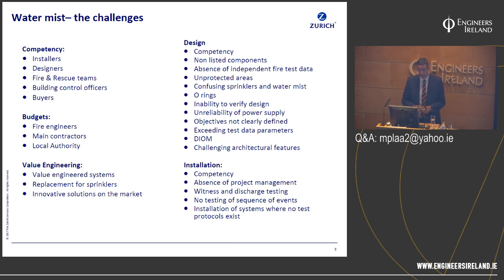And one of the things we find within Zurich in the field is that the fire and rescue officers and the building control officers do not really have a great deal of experience in the field of water mist. And as such, because of that lack of experience and deep involvement, it appears that they are signing off systems, accepting systems that are below par and may have some fundamental flaws. And I'll go on to show you some case studies where we've highlighted major issues with systems which have been signed off by an authority having jurisdiction and not knowing that there are actually issues with the system.